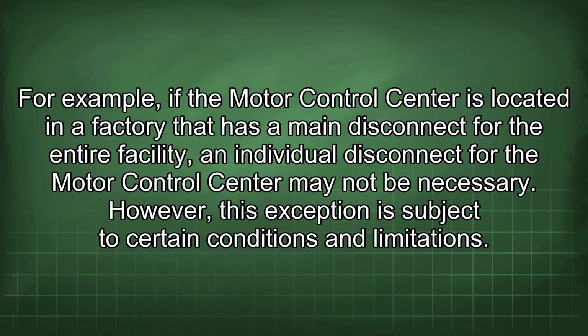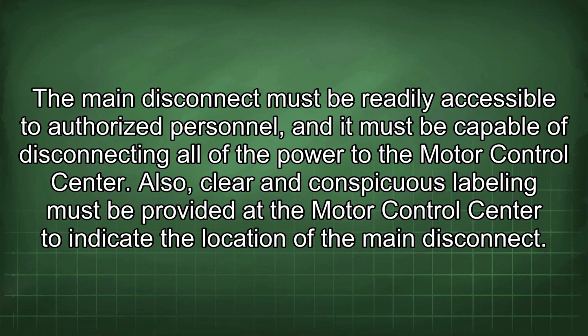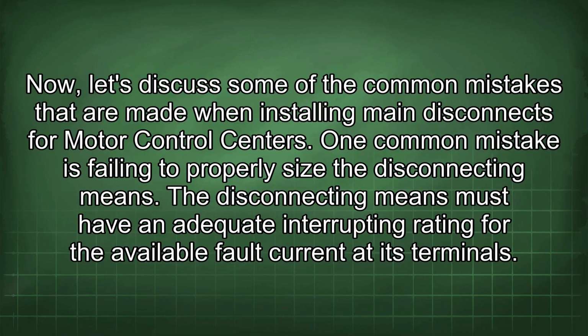For example, if the motor control center is located in a factory that has a main disconnect for the entire facility, an individual disconnect for the motor control center may not be necessary. However, this exception is subject to certain conditions and limitations. The main disconnect must be readily accessible to authorized personnel, and it must be capable of disconnecting all of the power to the motor control center. Also, clear and conspicuous labeling must be provided at the motor control center to indicate the location of the main disconnect. Now, let's discuss some of the common mistakes that are made when installing main disconnects for motor control centers.